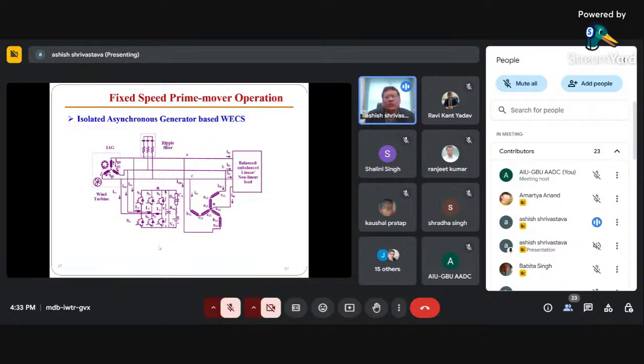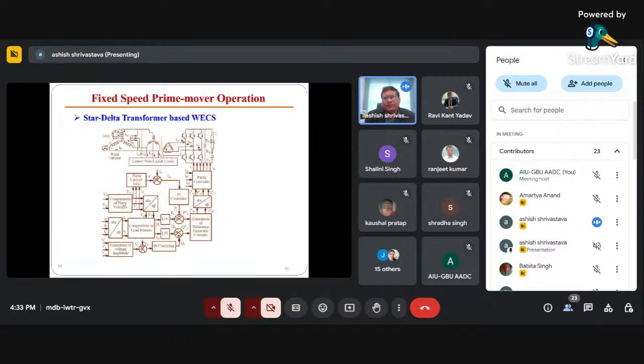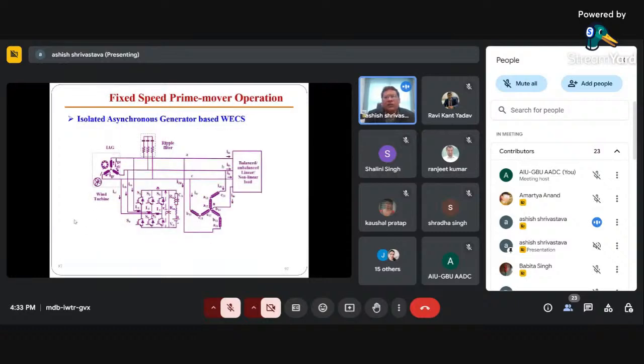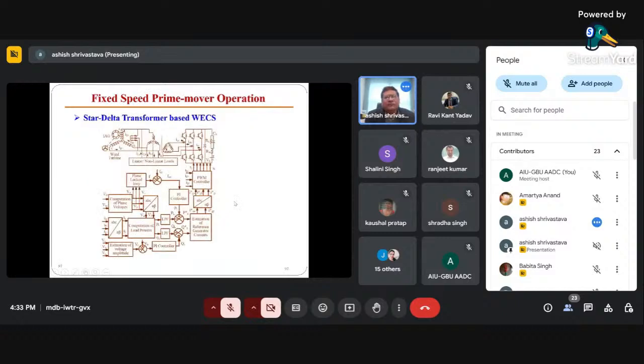This is another topology with a zigzag transformer. This transformer, known as the zigzag transformer, is connected on the load side, and according to the requirement the purpose will be served, whether charging the battery, feeding, or compensating the reactive power requirement of the load. These all have been reported in the paper.